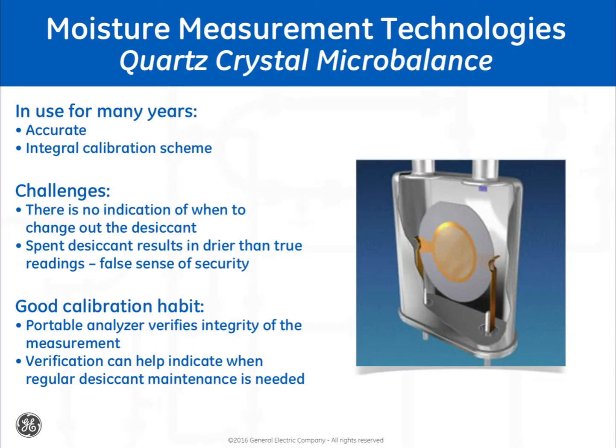Quartz crystal microbalance technology has been in use for many years. This technology's accuracy is sustained by regularly adjusting its calibration, and thus these analyzers come equipped with an integral permeation tube-based 1 or 2 point calibration scheme. The permeation tube requires that the process gas be dried below the calibration point to be generated. This can be considered the zero gas. This is accomplished by using a desiccant. Since there is no practical method to check the integrity of the desiccant, an operator could doubt the integrity of the calibration scheme and thus the measurement.